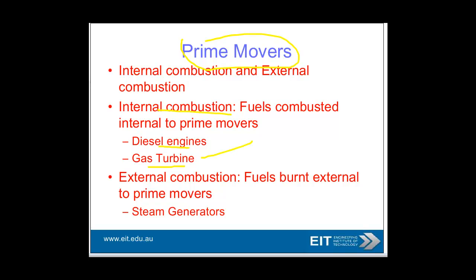And also, one power station I commissioned, we had the gas turbines, the 3 gas turbines, generating about 30 megawatts, I think it was, and you had a diesel engine which was there to provide the auxiliaries with power. So you power the diesel engine, and then that gets all the auxiliaries running for the gas turbines, which then leap into life, and then you close onto the grid.